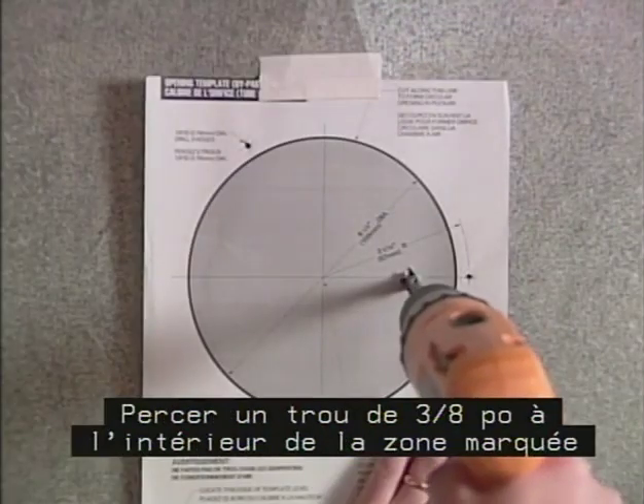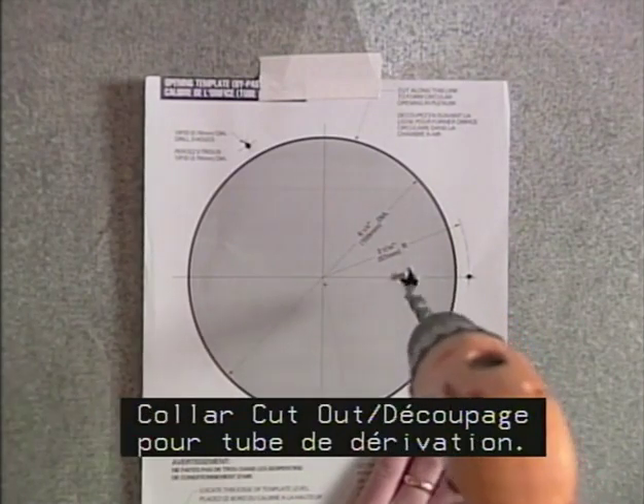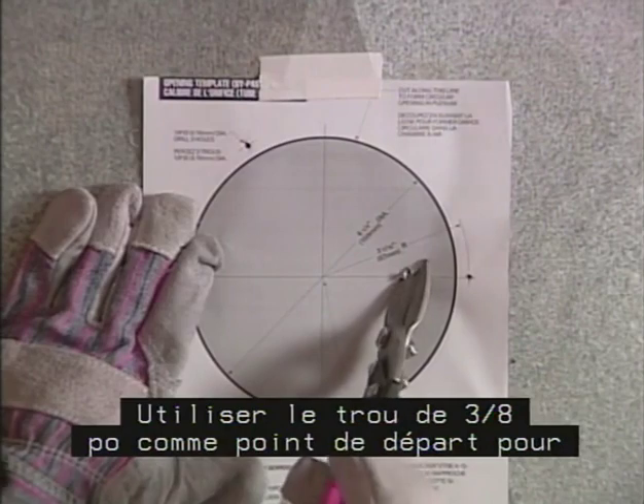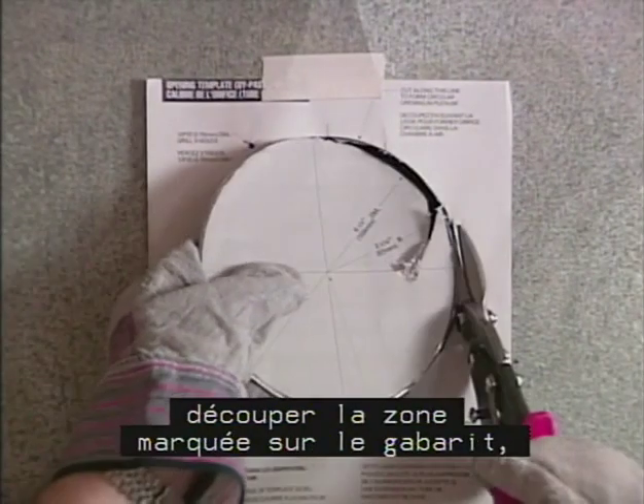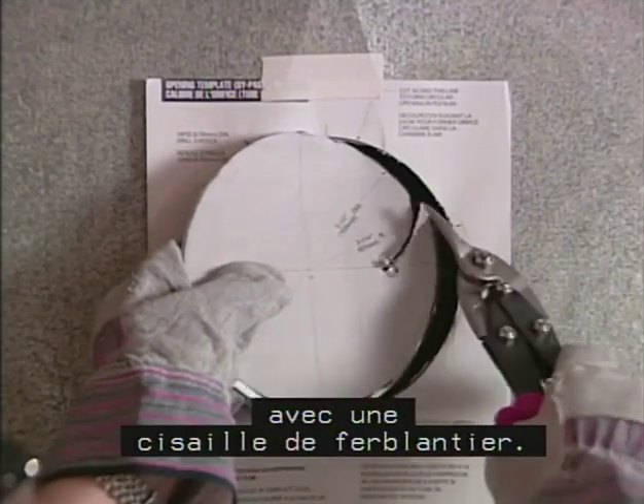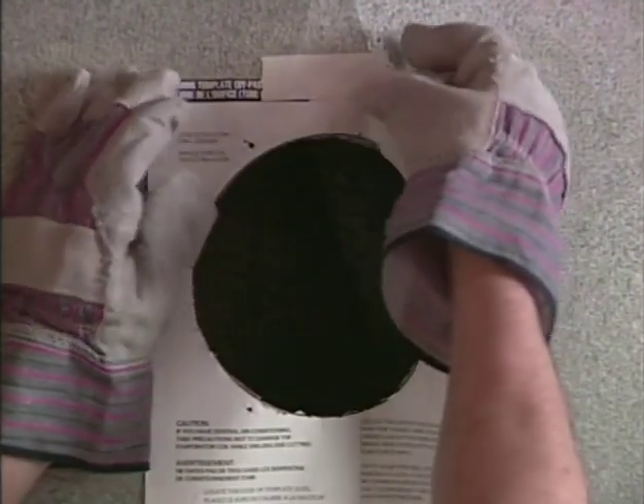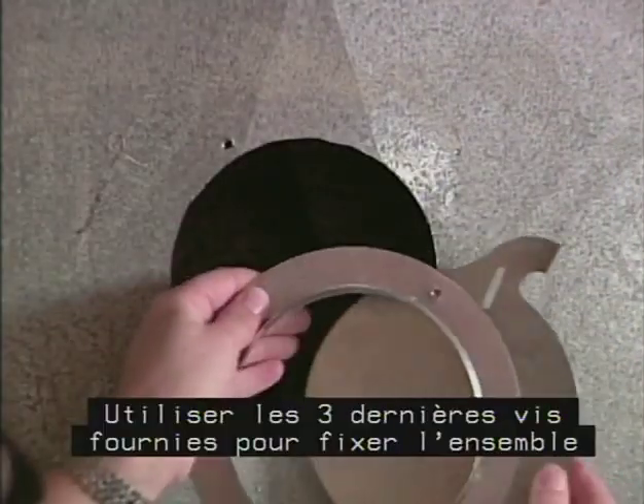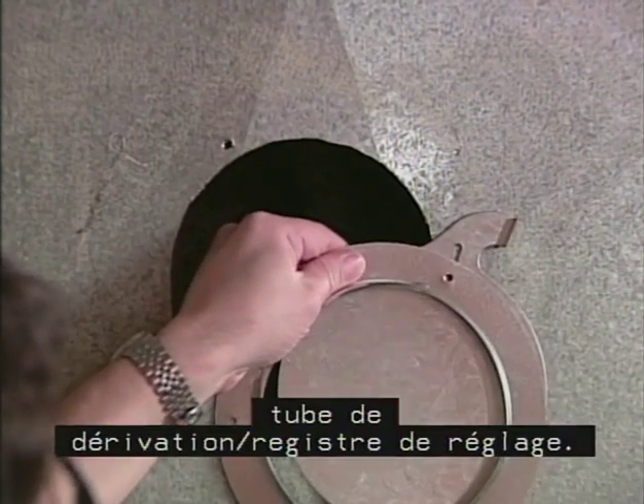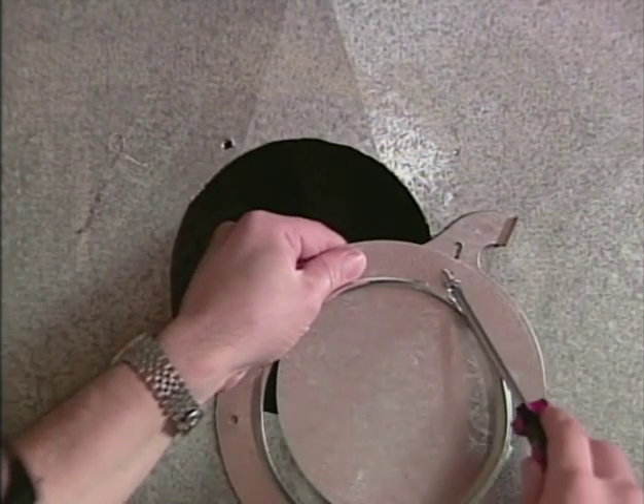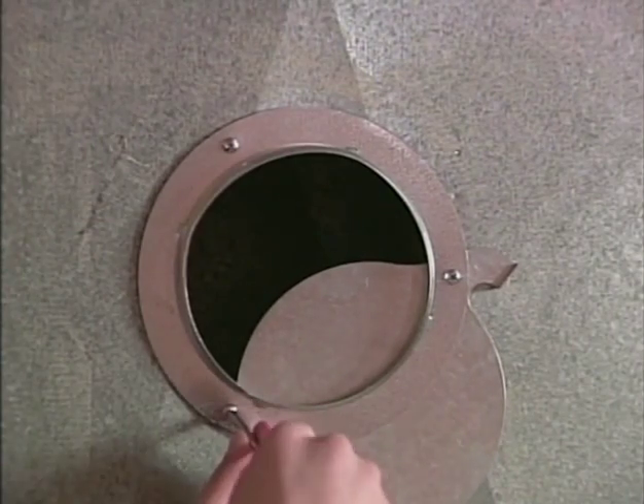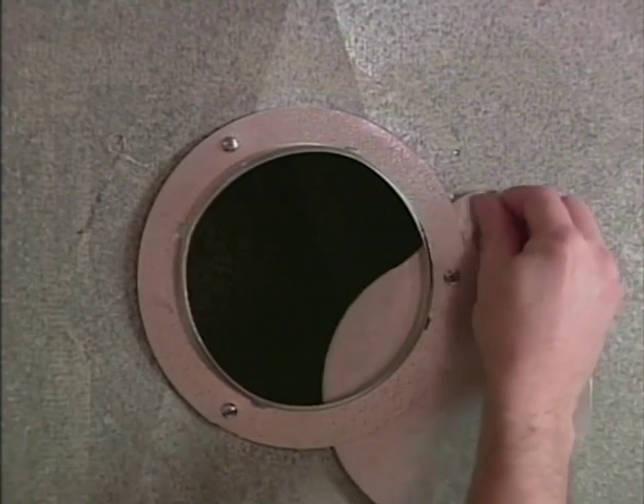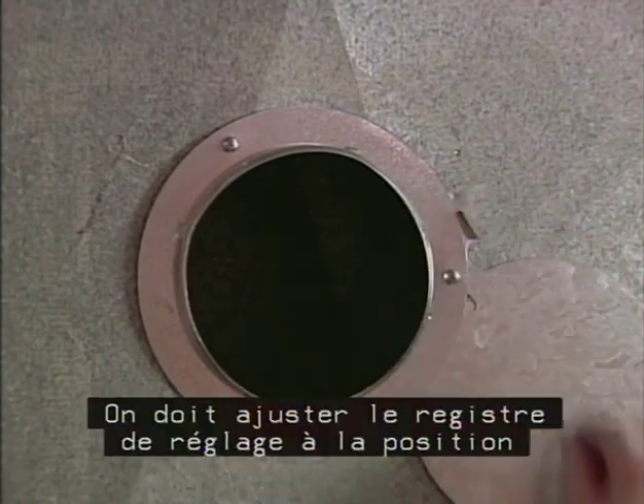Drill a 3/8 inch hole inside the area marked collar cutout. Using the 3/8 inch hole drilled earlier as a starting point, cut out the collar cutout area marked on the template using tin snips. Mount the bypass collar and damper using the remaining 3 screws from the installation package. The air damper should be mounted in the open position, securing it with the top screw.